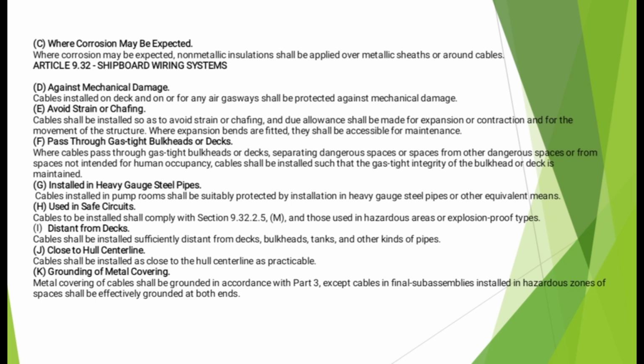Avoid strain or chafing. Cable shall be installed so as to avoid strain or chafing, and due allowance shall be made for expansion or contraction and for the movement of the structure where expansion joints are fitted. They shall be accessible for maintenance. Pass-through gas-tight bulkheads or decks. Where cables pass through gas-tight bulkheads or decks, separating dangerous spaces from the other dangerous spaces or from spaces not intended for human occupancy, cables shall be installed such that the gas-tight integrity of bulkhead or deck is maintained. Installed in heavy gauge steel pipes. Cables installed in pump rooms shall be suitably protected by installation in heavy gauge steel pipes or other equivalent means.